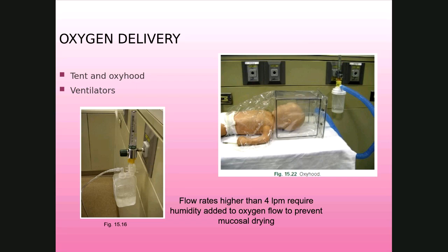So they don't do that anymore, but these oxy hoods, like you see here, those you might find in a NICU or in a pediatric unit where the baby's head is in there. It looks barbaric, kind of, but the oxygen is delivered in here so that the baby has a constant supply, because you're not likely to get a mask on a baby. Not going to have them stay with a mask on their face, so these oxy hoods serve that purpose.